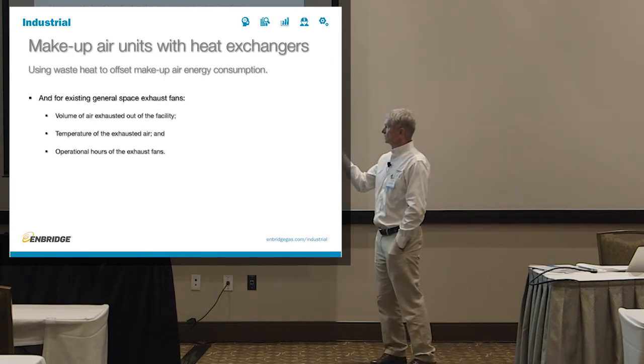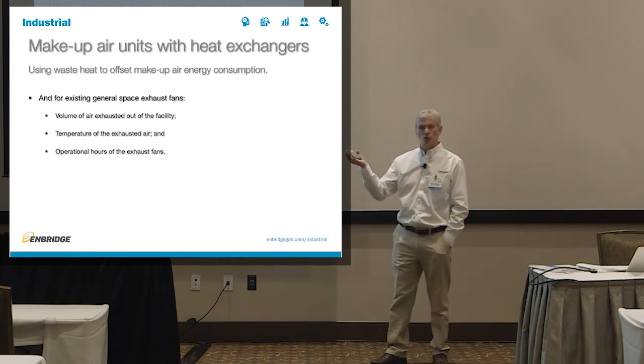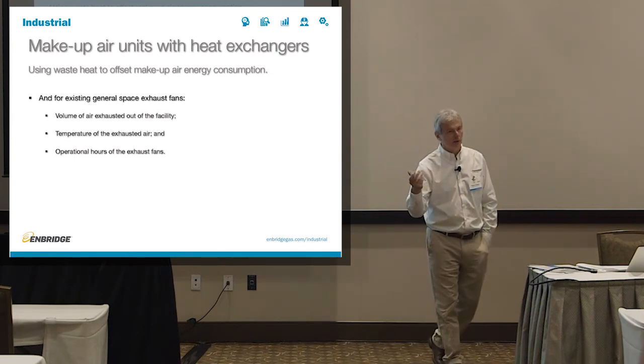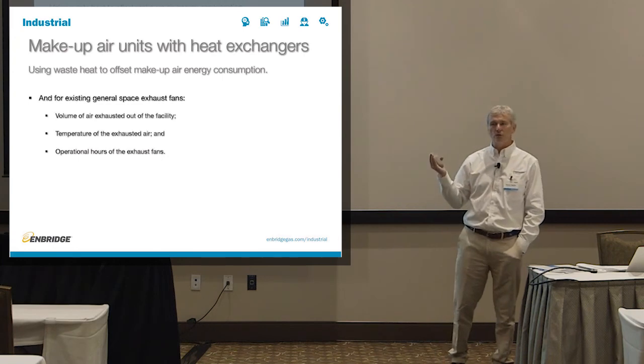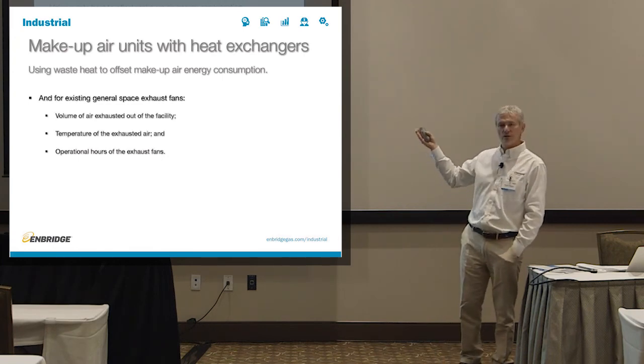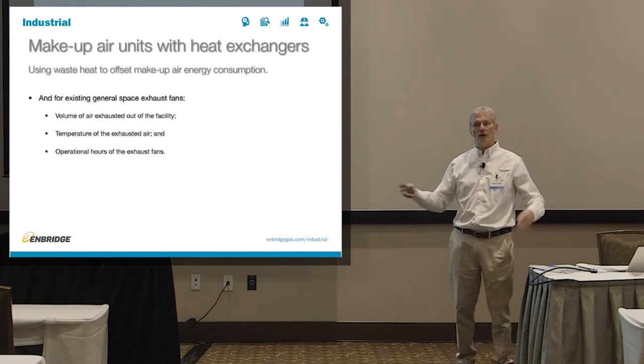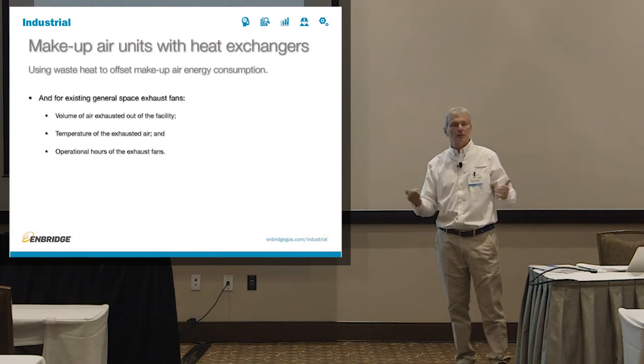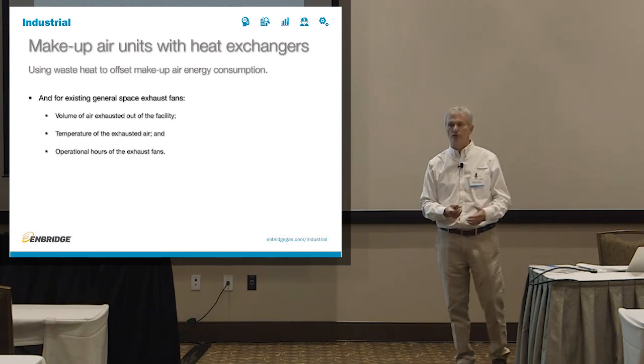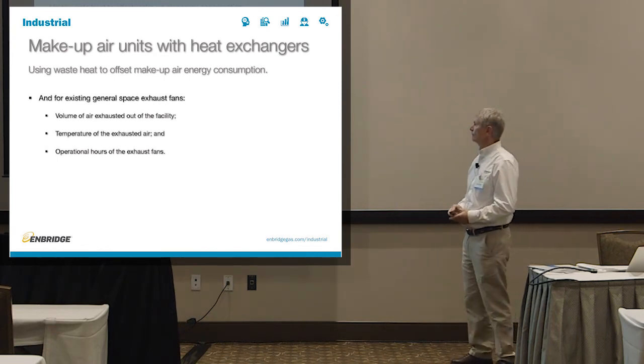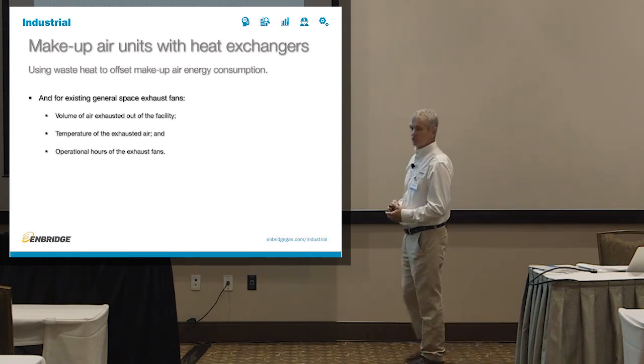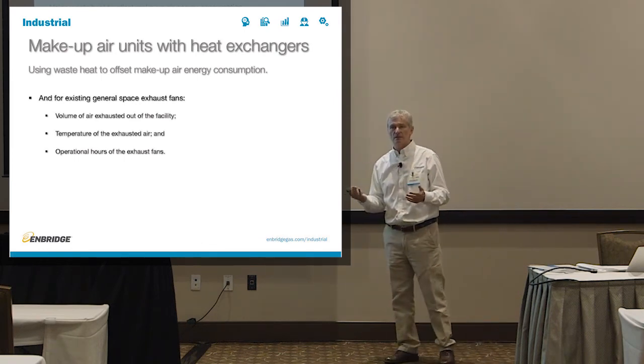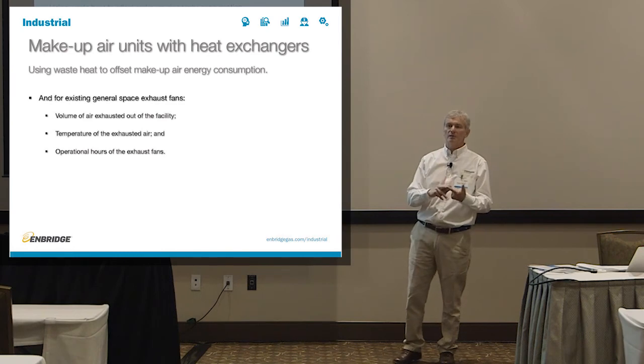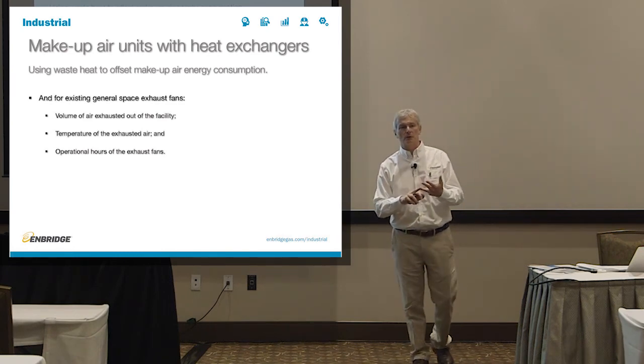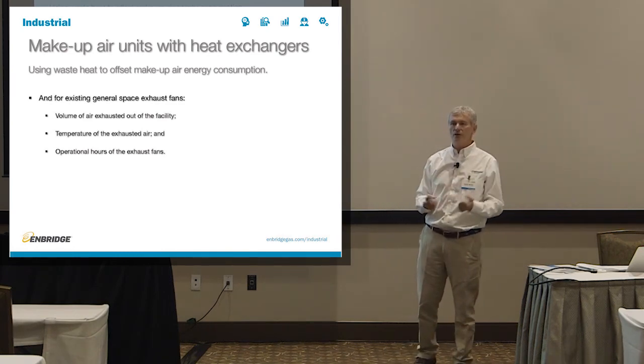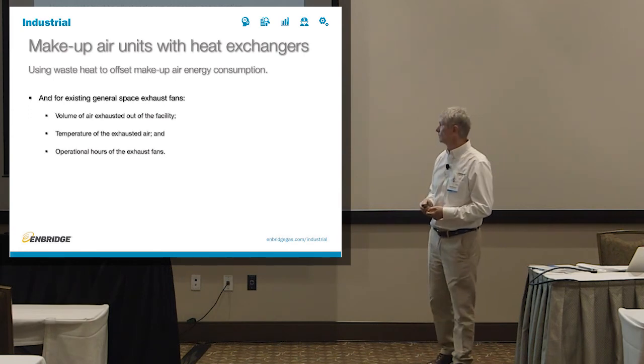For the exhaust, same thing. Volume of air exhausted, temperature of the exhausted air. If it's too difficult to figure it out, you can just assume that you're exhausting the air at the same temperature you have at the facility's level. So if it feels like 18 degrees Celsius, that's probably what your exhaust is like. Operational hours of the exhaust fans. Again, same thing: 1.08 times CFM times delta T times number of hours. That's all you need for any of those formulas.